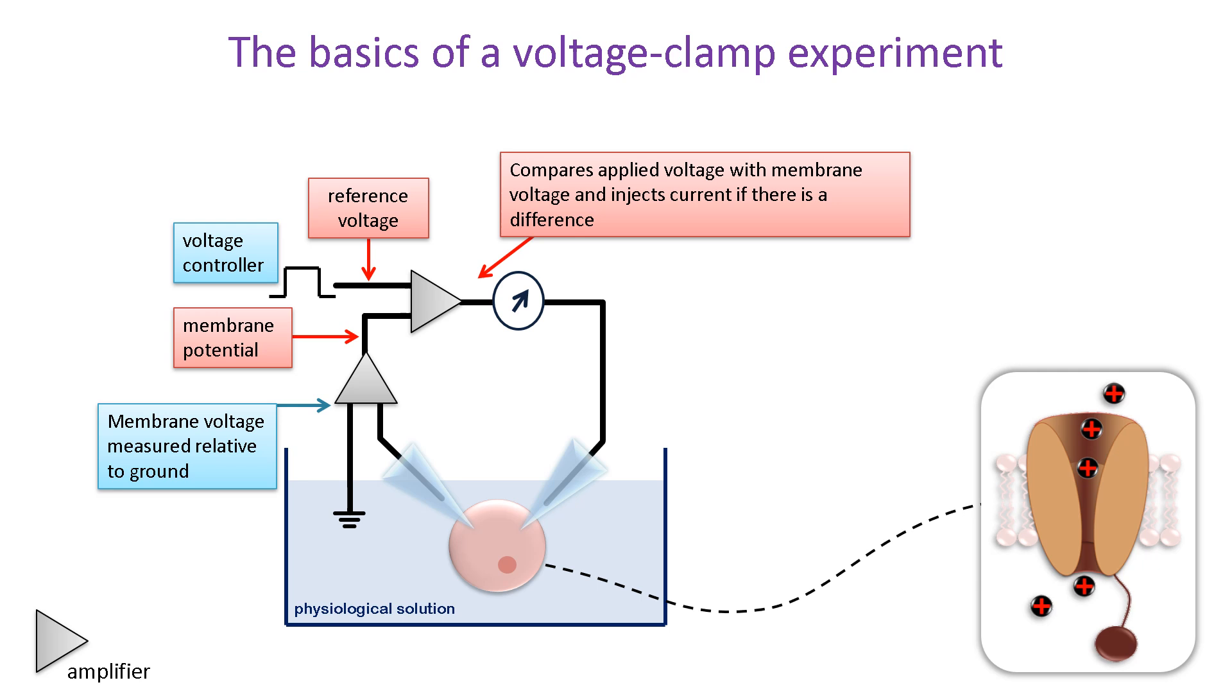The output of the amplifier measures the membrane potential and is fed into a second amplifier. It compares the measured membrane potential with a reference voltage at which the membrane is to be clamped. Its output is proportional to the difference between the two values. So, when the membrane potential equals the reference voltage, the output is zero. When ion channels open and pass current, it induces the membrane potential to change, causing the amplifier to emit current to bring the difference back to zero. Its output current is fed back into the cell via a second electrode to recover the membrane potential to the reference value.